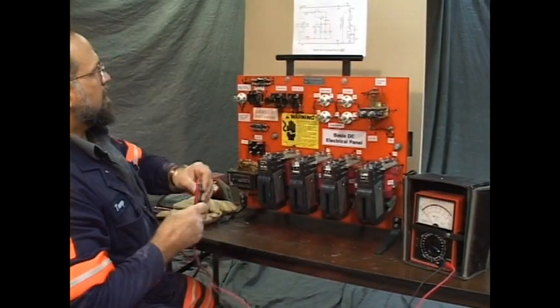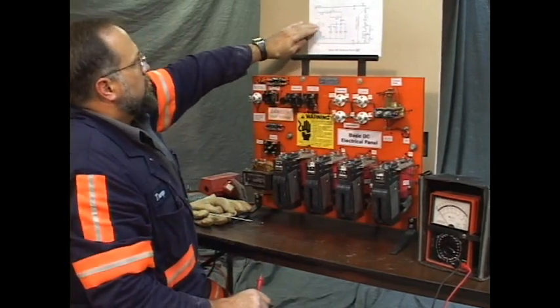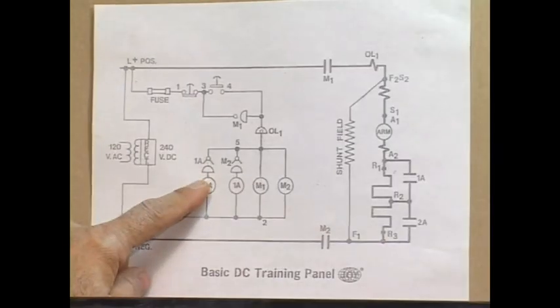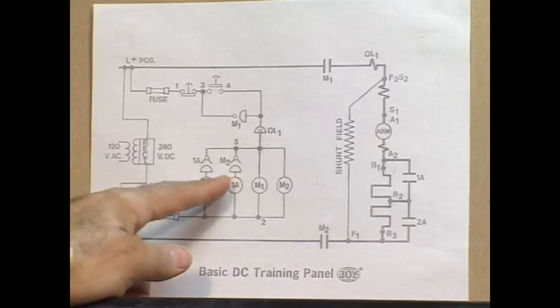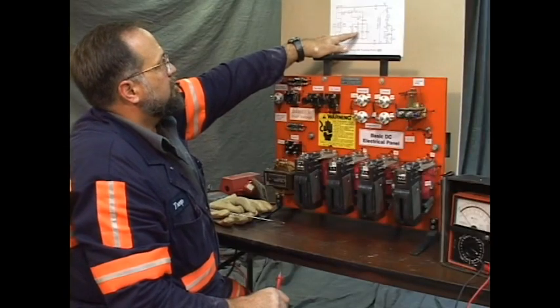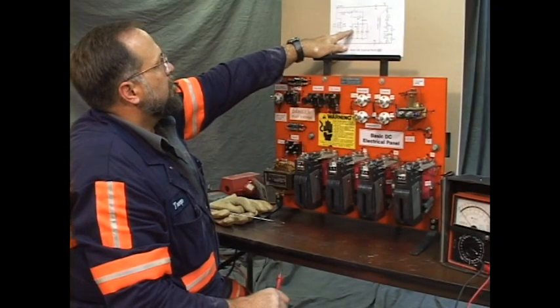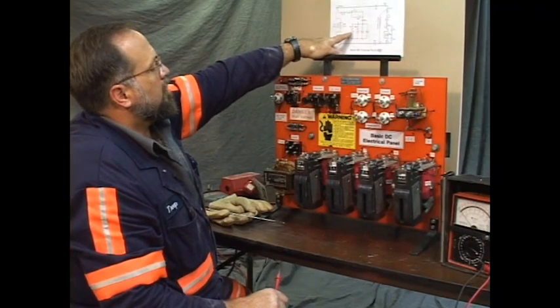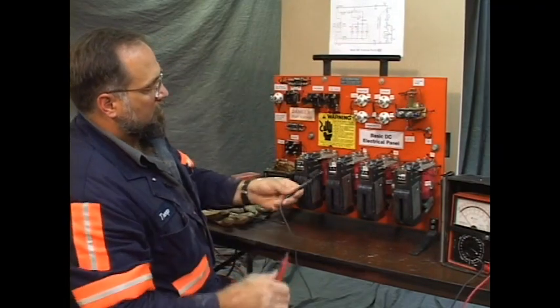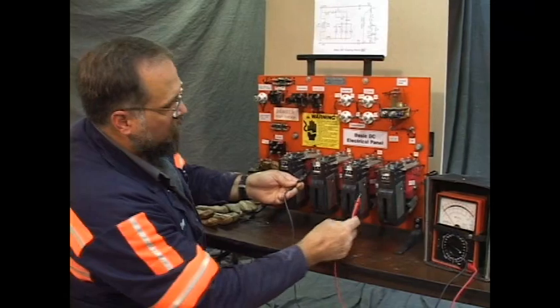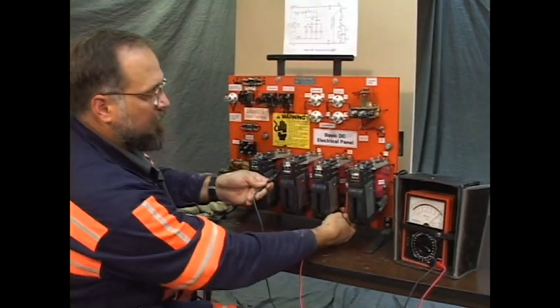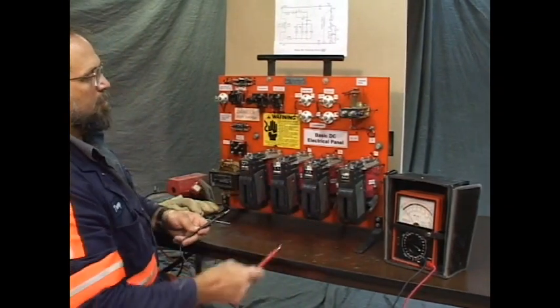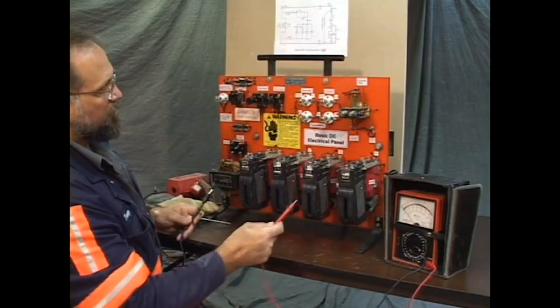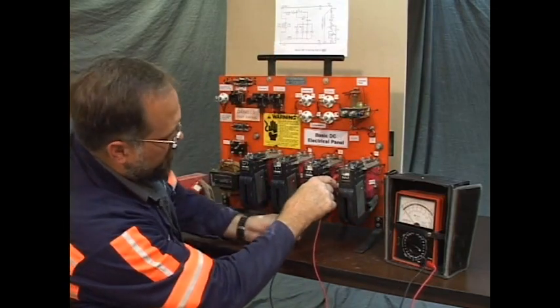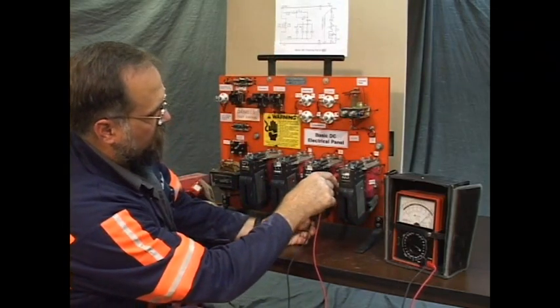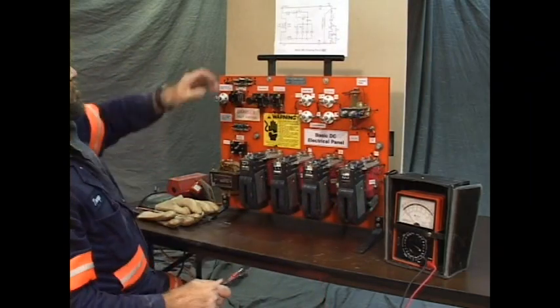We have checked the entire positive portion of the control circuit with the exception of these two small wires. They're small on the drawing, but in fact they're as long as any of the others in real life on the panel. The bottom of the 1A mercury tube to the positive of the 2A coil. Here we go. The positive of the coil. It's intact. And the bottom of the M2 mercury tube to the positive of the 1A coil. And there you have it.